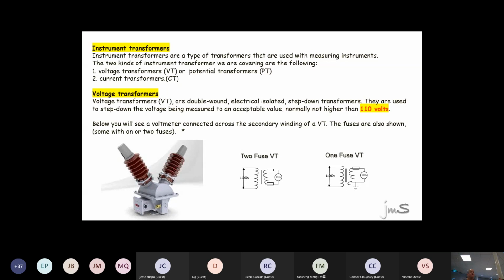But before I do that, can you all see there's 2 types of VT symbols? The one over here with 2 fuses and one with 1 fuse. If you earth one side, you only have 1 fuse. If you don't earth it, you have to have 2 fuses. No law says which one to use. There's no wrong or right. The choice is the manufacturer's.